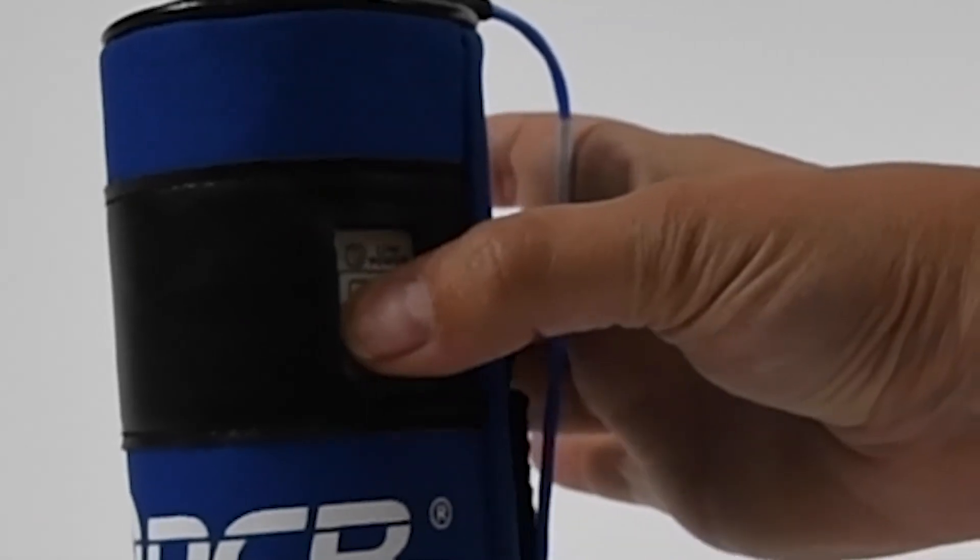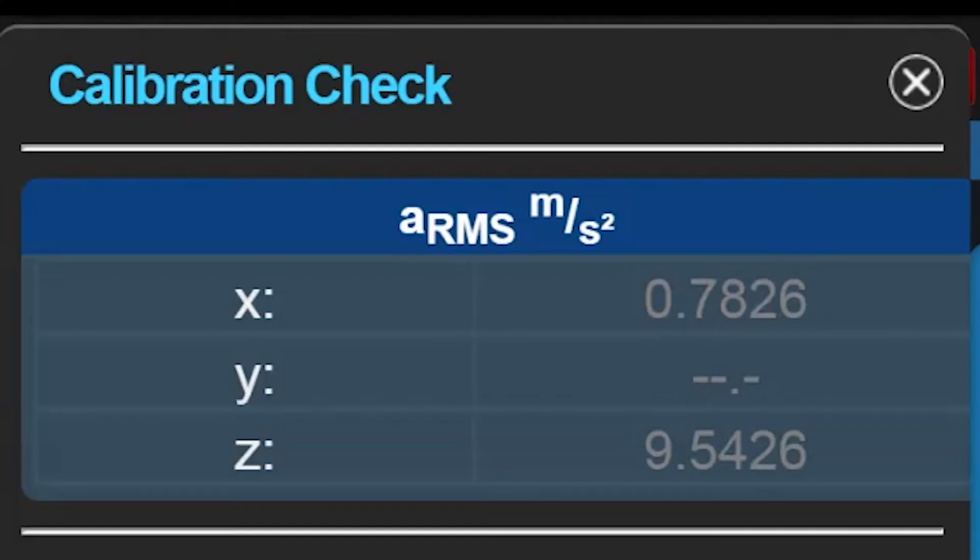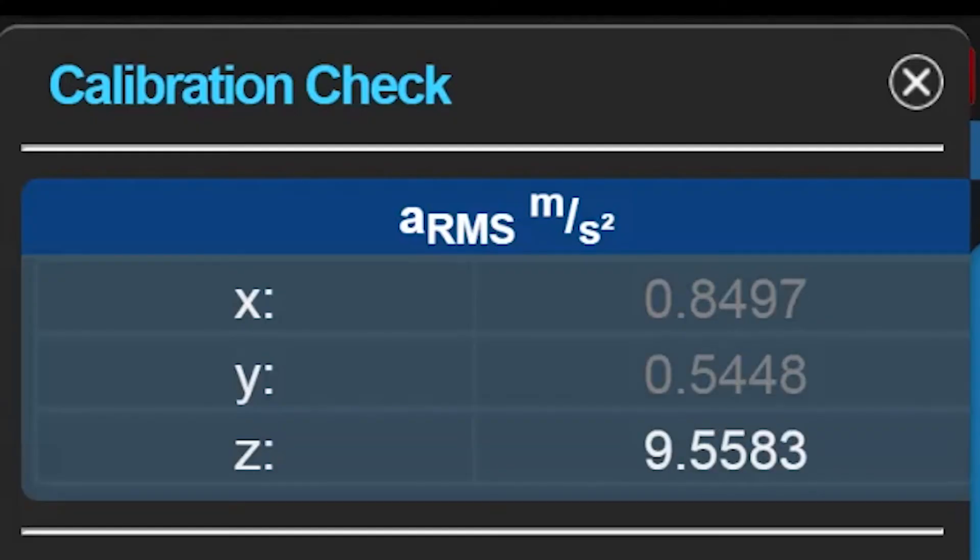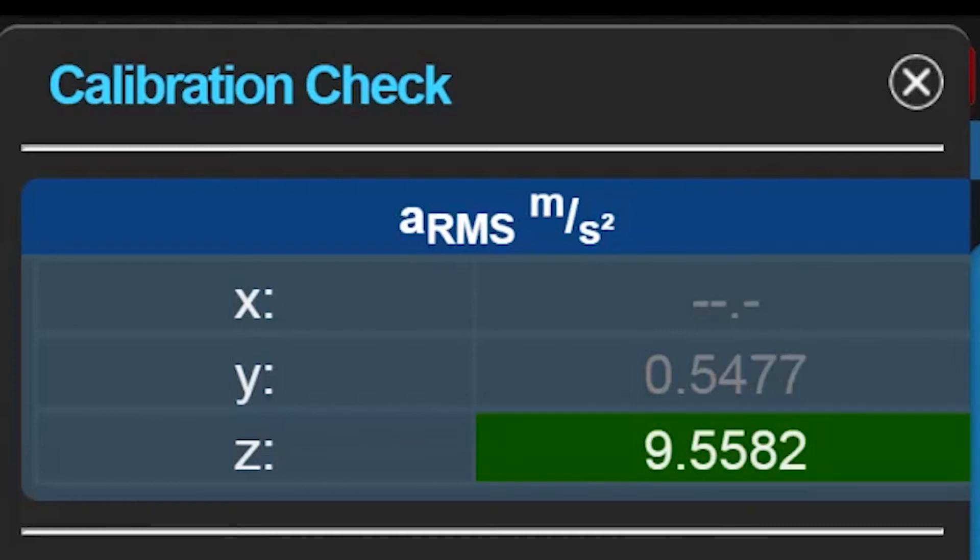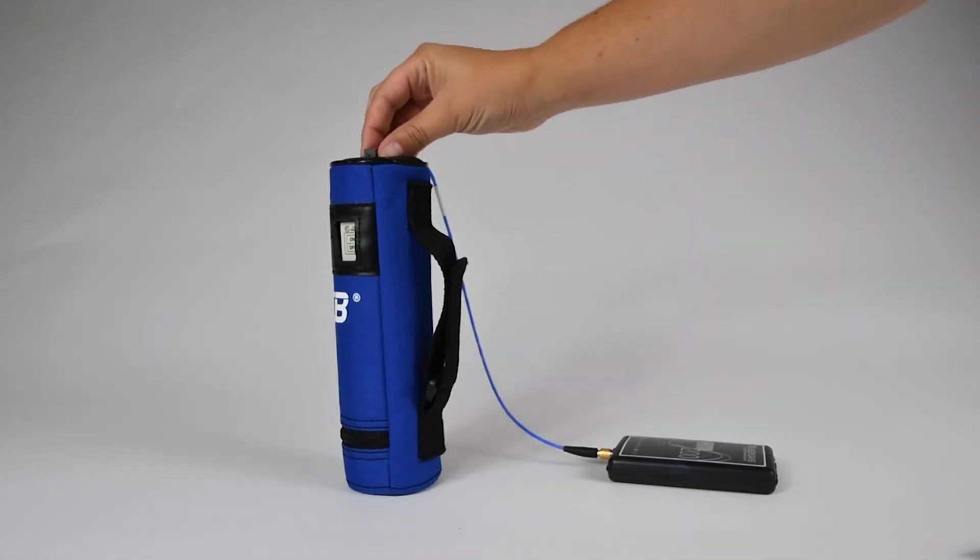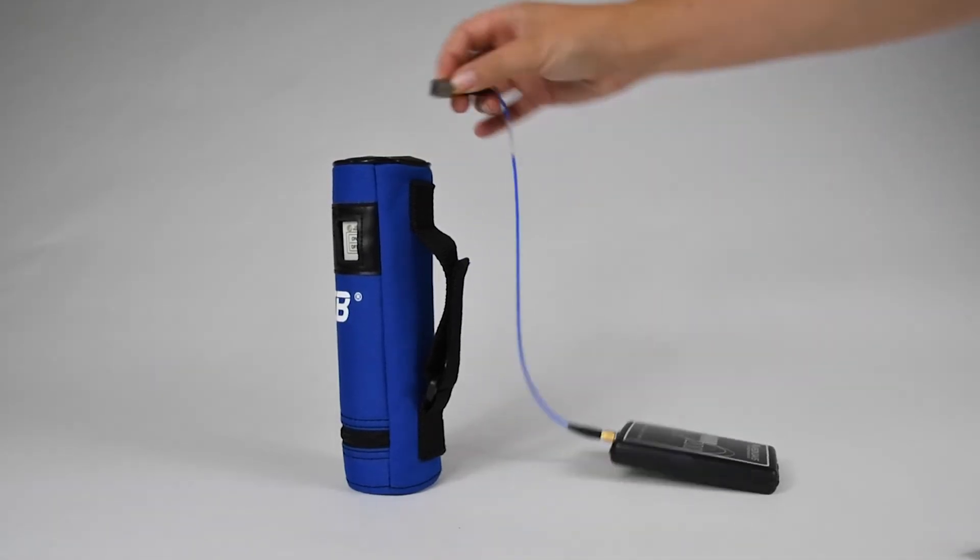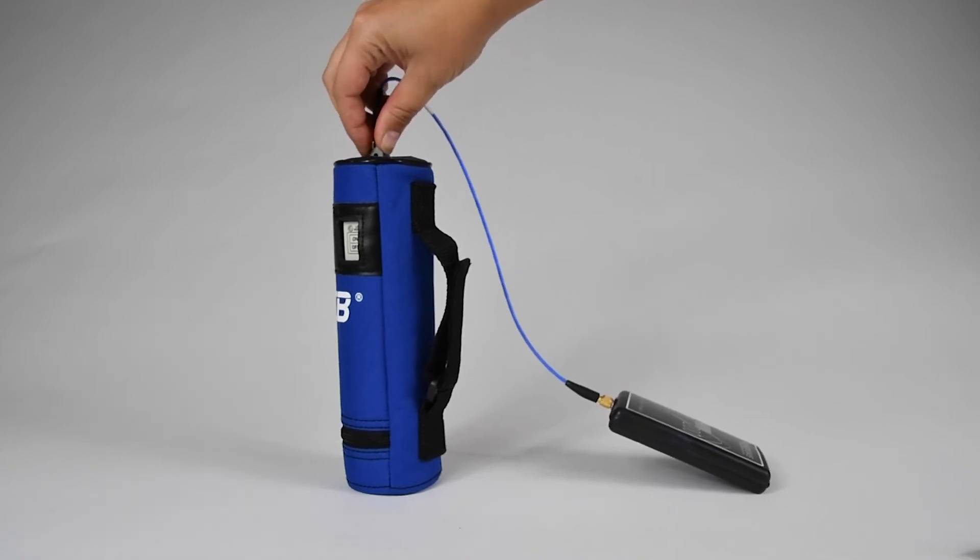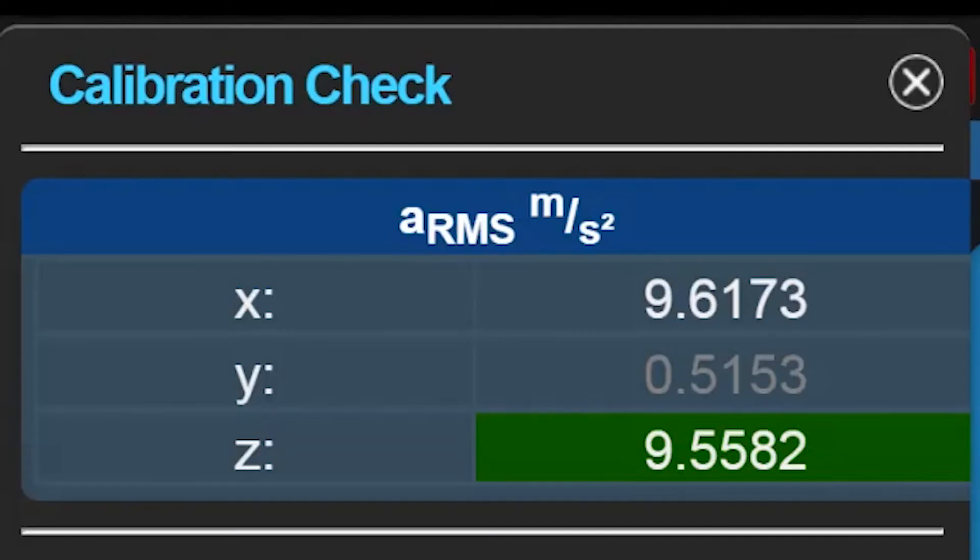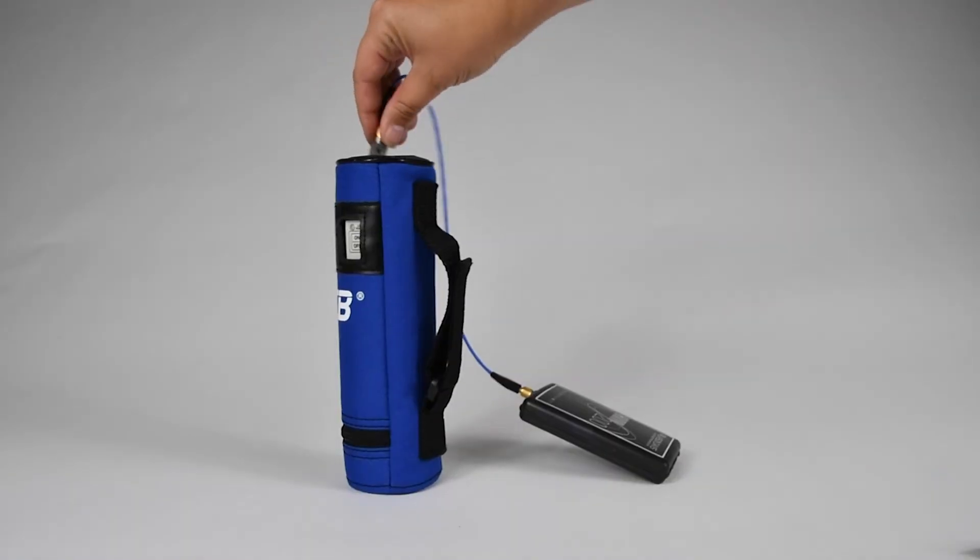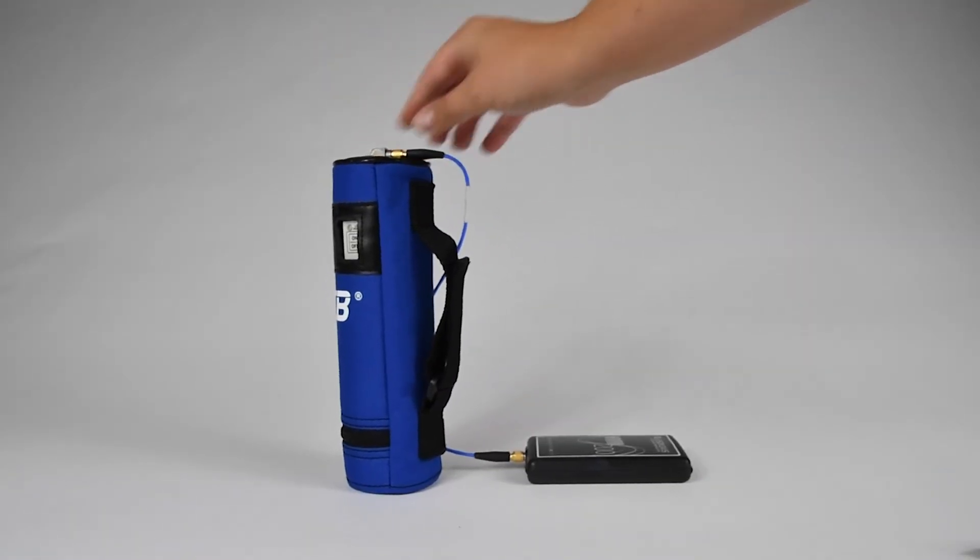Start the shaker and note the ARMS values for each axis. They are as follows. Values are gray when the level has not been checked. Values are white when the level is being checked. The cell will turn to green when the axis measurement is complete and the level is within plus or minus 5% of the reference value. It will be red if the level varies from the reference value by more than plus or minus 5%.